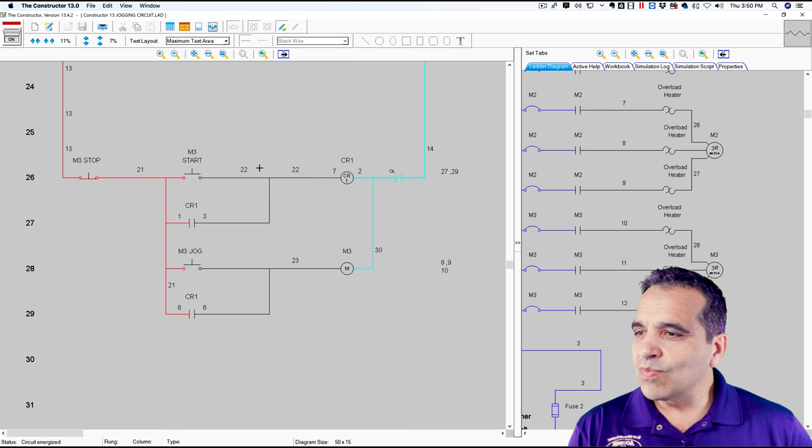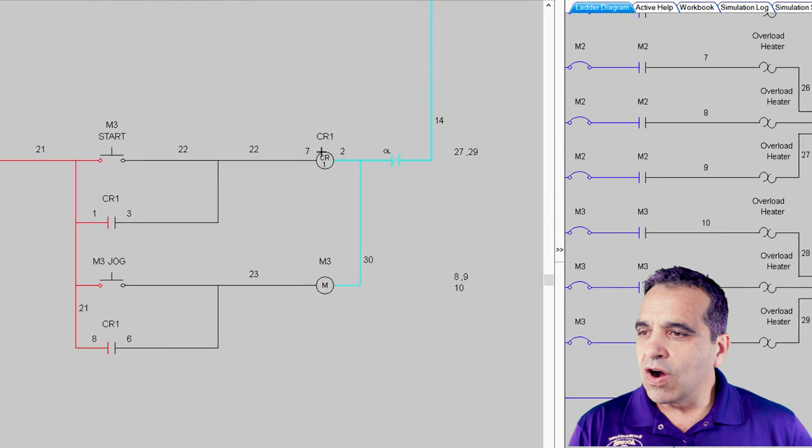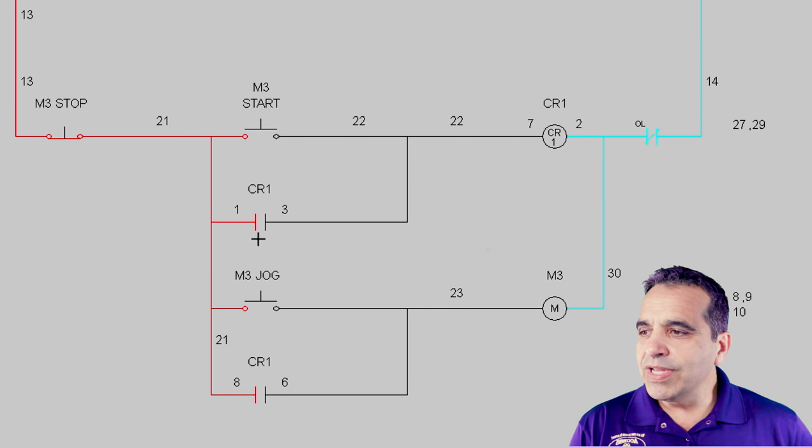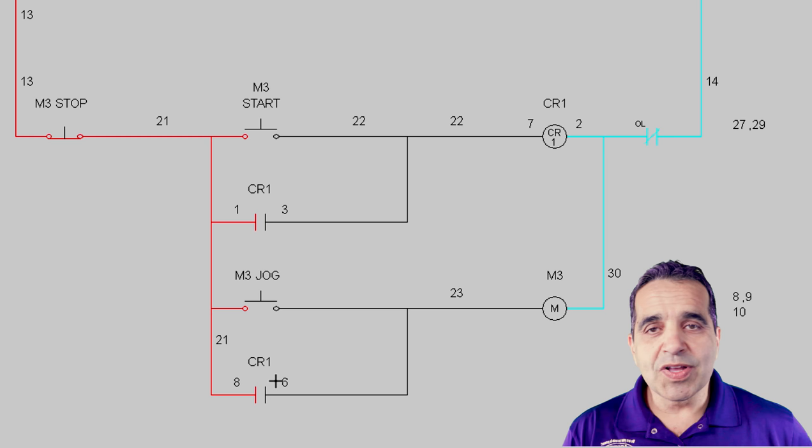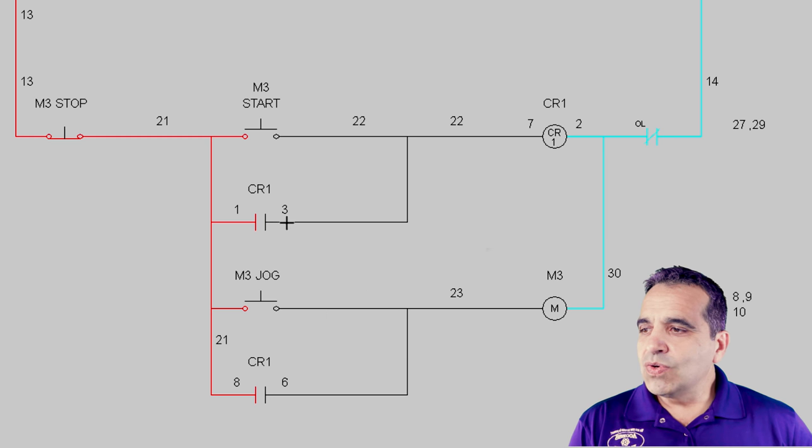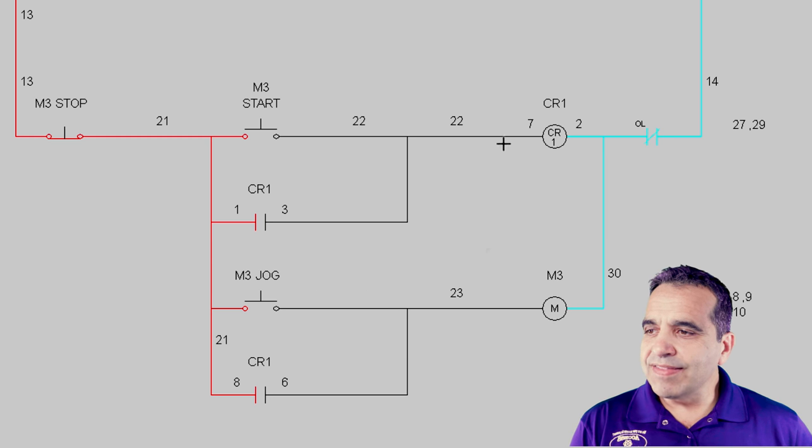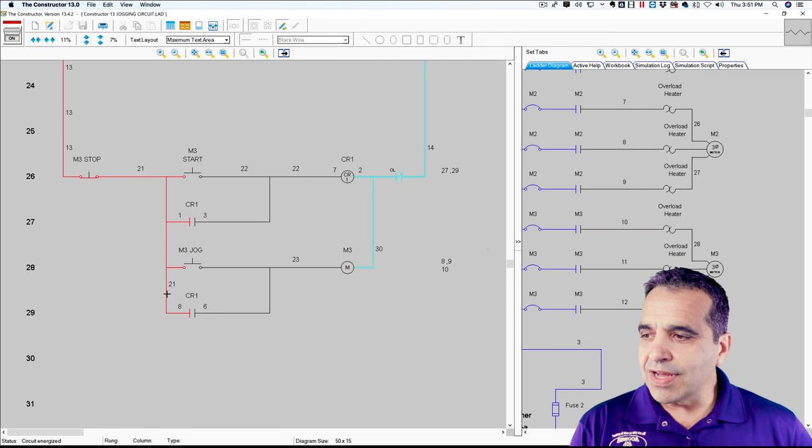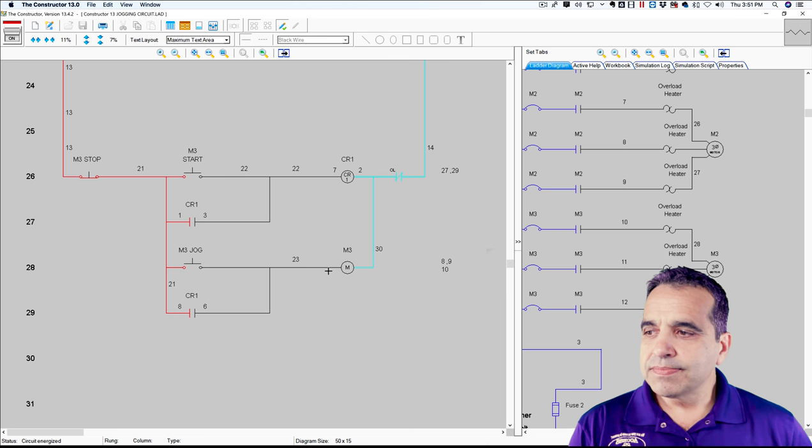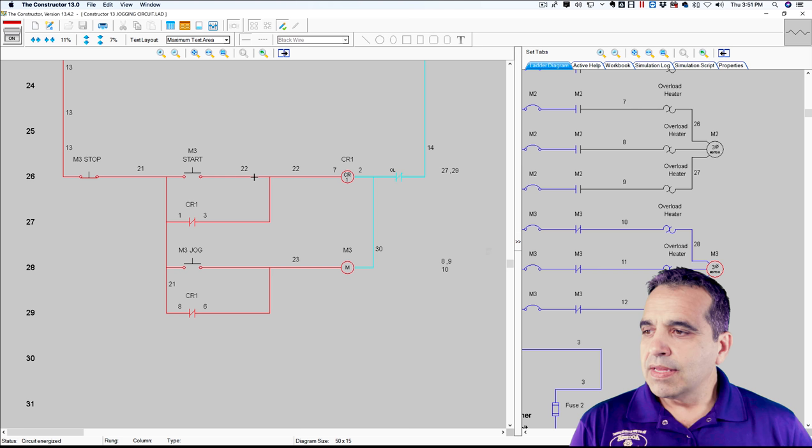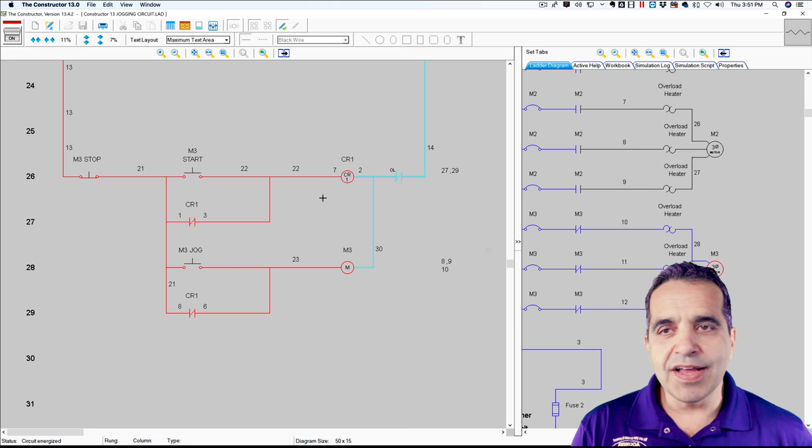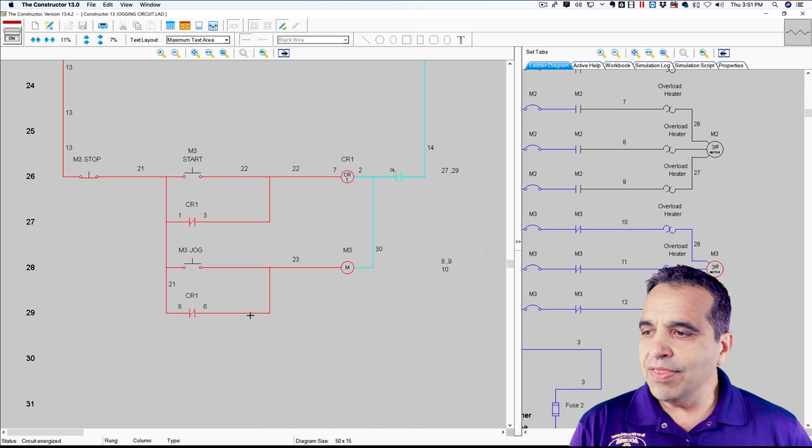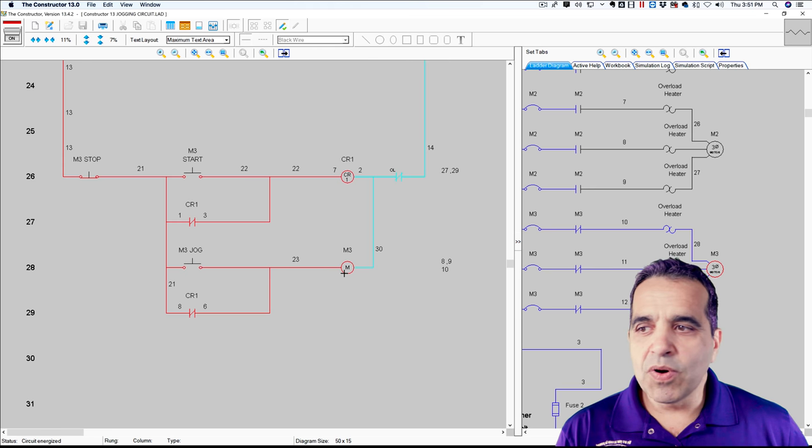So what we're doing is we're energizing our ice cube relay. Our ice cube relay, we're using one and three, which was normally open and eight and six, which was normally open. One of those contacts is keeping itself on. So that becomes our holding contact. The other contact actually will start our motor. And so hit start. The coil, the ice cube relay energizes, closing the holding contact, keeping itself on and also closing the other set of contacts, turning on the motor.